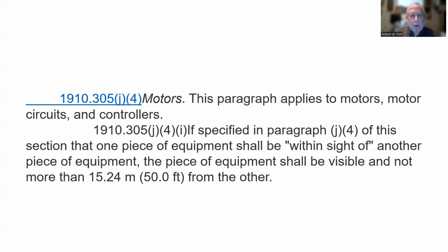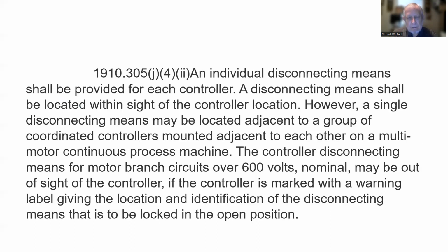This paragraph applies to motors, motor circuits, and controllers. If specified in paragraph J4 of this section that one piece of equipment shall be within sight of another piece of equipment, the piece of equipment shall be visible and not more than 50 feet from the other. So within sight of means visible and within 50 feet. And that makes sense. An individual disconnecting means shall be provided for each controller. A disconnecting means shall be located within sight of the controller location.